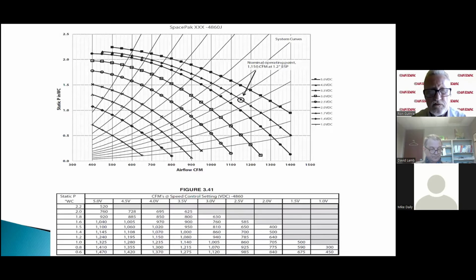All right. So, for instance, this is a 4 or 5 ton unit. If we wanted to be at 1250 CFM on this, we would look at 1250 on the bottom, draw the line up to that 1.3 static, and that would tell us that really for 1250 we want to be at a 5.0 volt DC signal. We would change the rheostat to send the signal, and we can measure right on those little tabs what that signal is. That's how we would determine what signal we want to use to run the fan at that particular speed for that particular mode. Now, it's all in chart form down below as well, so you can either look on the graph or look at the chart to determine what you wanted to run.